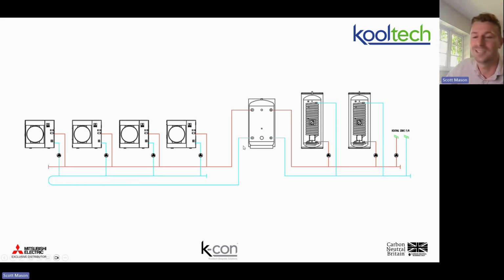However, our heating circuit originally was going to be 40, 35. We're now producing 55 when we don't need to. So our overall system efficiency has probably come down slightly. And someone's now got to wire in 4 units with 4 circulating pumps, which means that basically we now need 8 penetrations to the building, whereas previously we only needed 2, albeit the pipework diameter will still be 2-inch on the common sections. So that's one way of doing it when capex or space are the major driver.